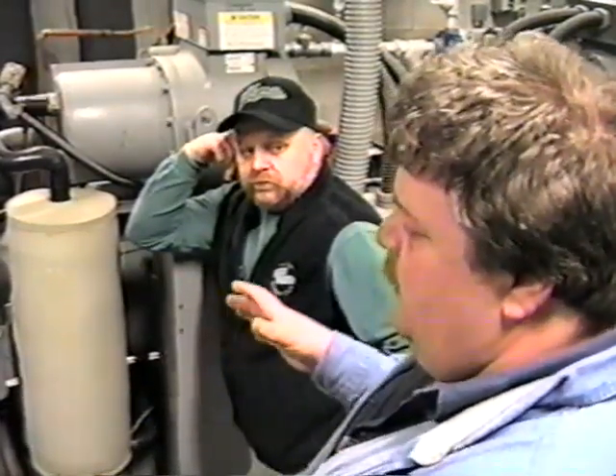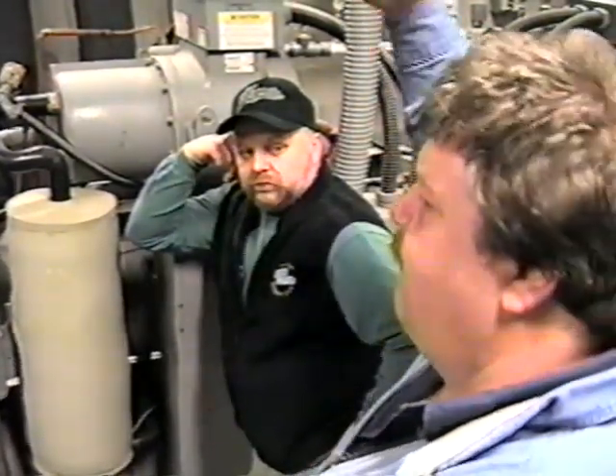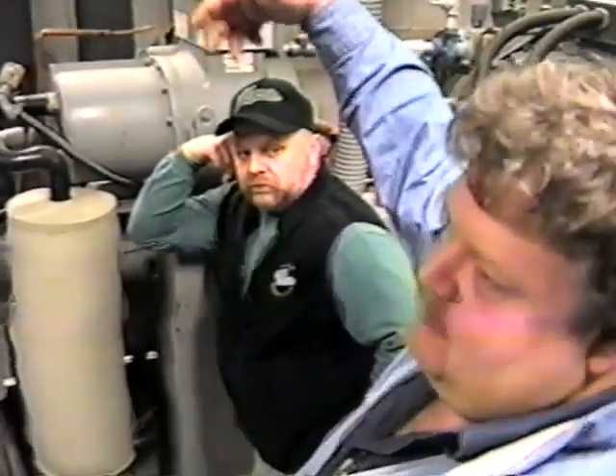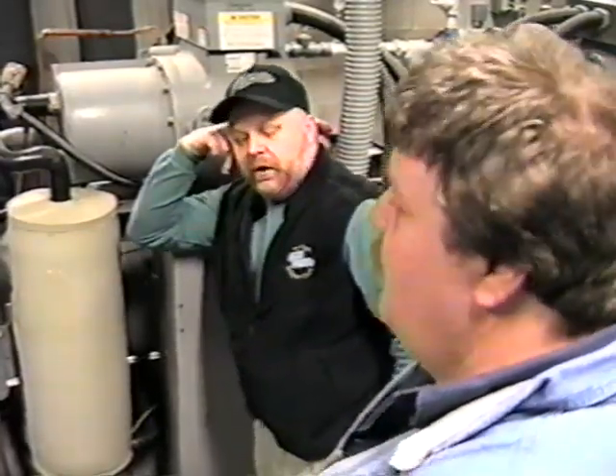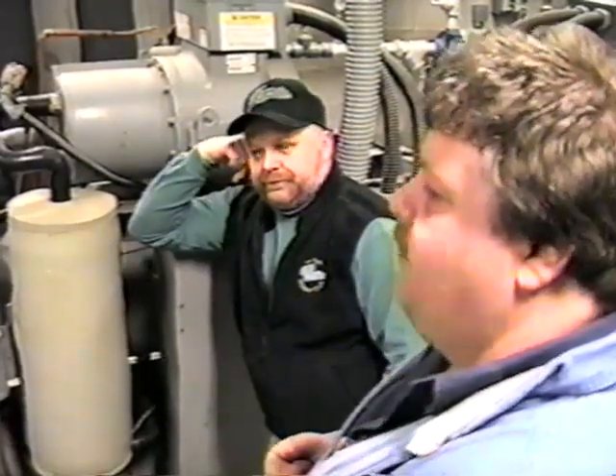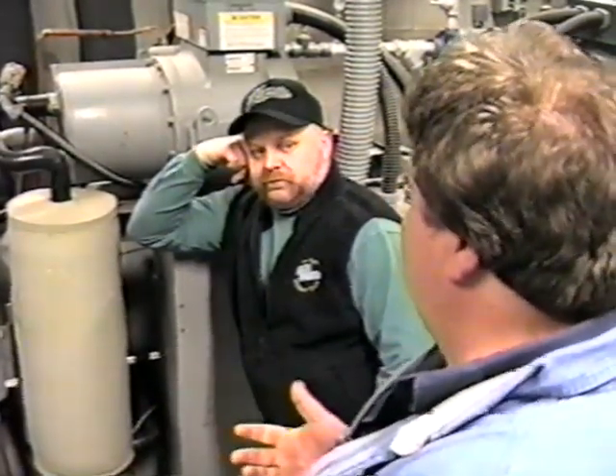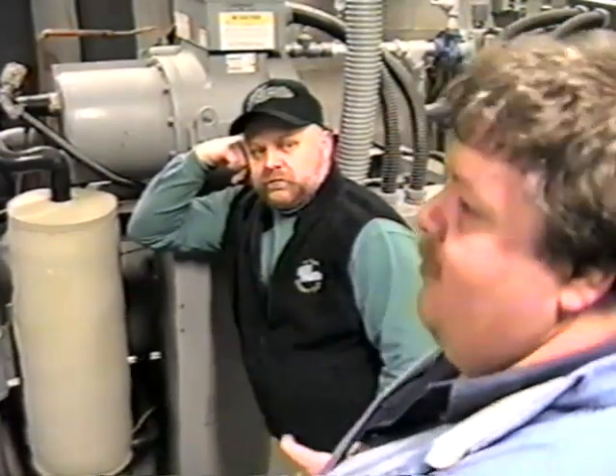What we do is we use a wide field of view on it so that we don't pick up nuisance things underneath it. Let's say the thing's 21 feet in the air, an easy number. We use a field of view of 3 to 1. So for 21 feet up, divide that by 3, and I've got a 7 foot circle on the ice that I'm looking at. So not just one person standing underneath is going to send the temperature up. The only thing you can put underneath it that's going to screw it up is the Zamboni if you park it underneath it. If you drive underneath it, it's not going to notice it.